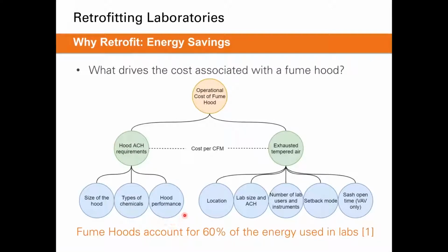And then also your hood performance. So if your hood requires a higher feet per minute or face velocity in order to maintain safe containment, then that would also drive up the overall air that's flowing through that hood as well. Moving on to what drives the amount of exhausted tempered air up, that is directly related to your geographical location due to the loads from the weather, and as well, this would also affect your energy prices, so your cost per CFM.